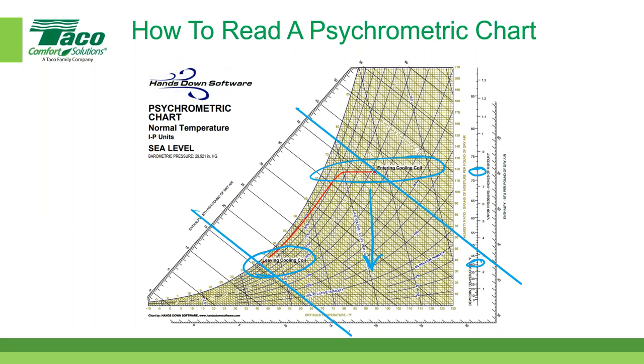So down here, let's say that H is the abbreviation for enthalpy, and I'm going to use the word approximate. This looks like it's about 42 BTUs per pound of dry air, and let's call that H1. And then H2 down here is about 16 BTUs per pound. Now, how much work did the coil do? Well, this is what I think John was getting at earlier. The amount of work the coil does is equal to the BTUs per hour. The BTUs per hour is equal to 4.5, and that's a constant, times CFM times delta H.